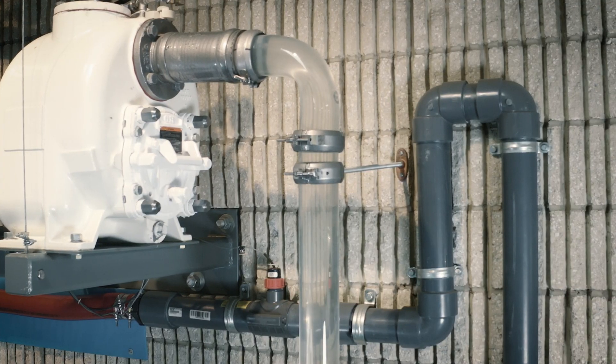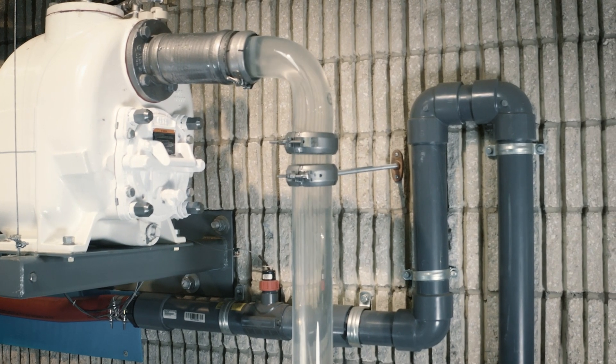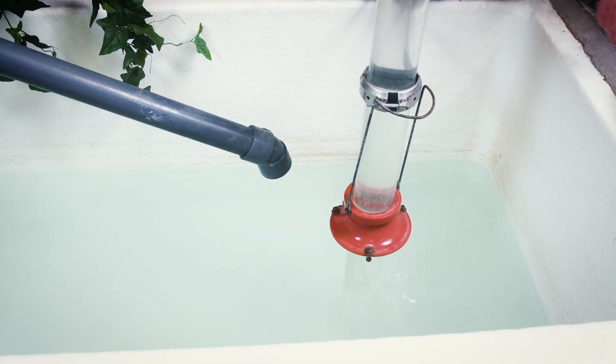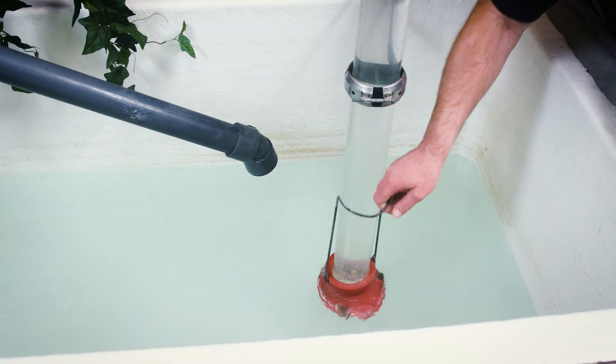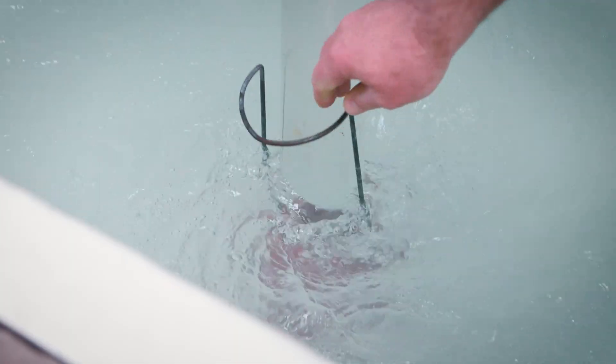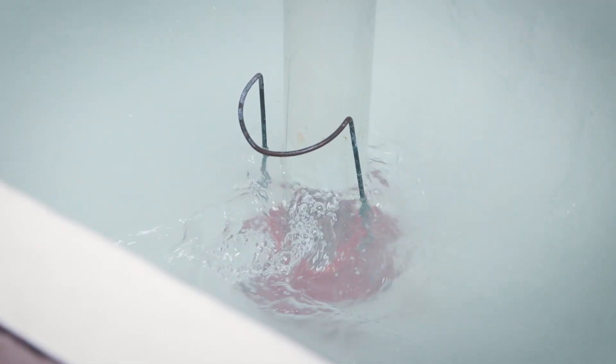This will impede the pump's performance and may cause it to lose prime. A flare attached to the end of the suction line reduces the entrance velocity of the liquid and reduces the level required in the sump to prevent vortexing.